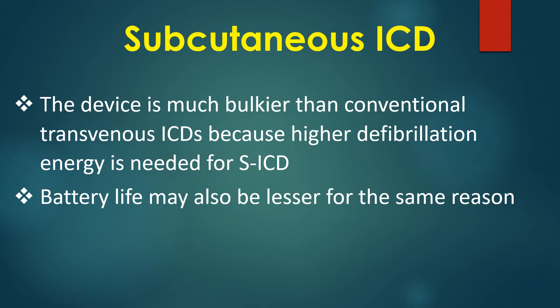The device is much bulkier than conventional transvenous ICDs because higher defibrillation energy is needed for SICD. Battery life may also be lesser for the same reason.